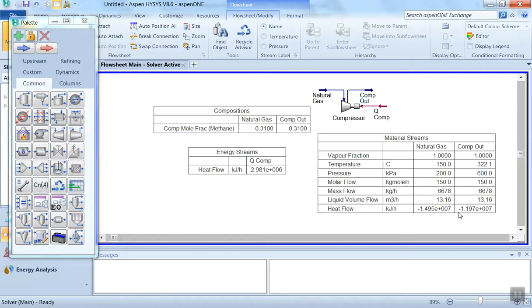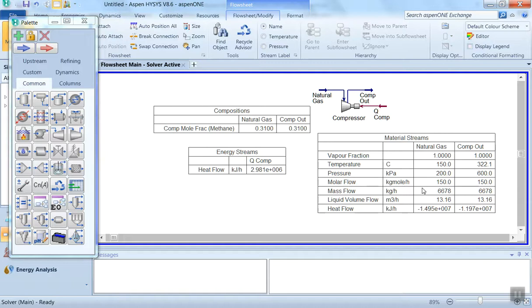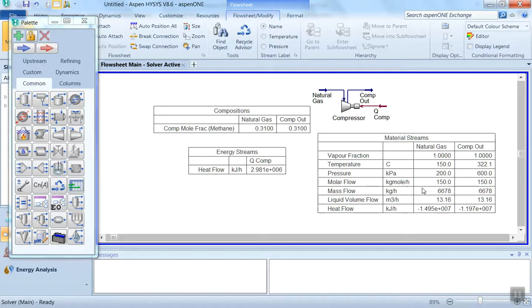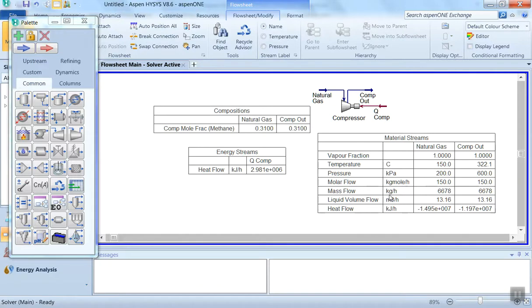The result shows that when the temperature of the natural gas increases, the outlet temperature also increases, and hence the effect to increase the compressor duty. Theoretically, the compressor is used to transport the fluid through the pipe using the rising pressure of that fluid and reducing its volume. On doing so, the temperature of the gas also increases, which depends on the percentage of the efficiency of the compressor. At high efficiency, the outlet temperature increment is lower as compared to the low efficiency system under the same mass flow rate.